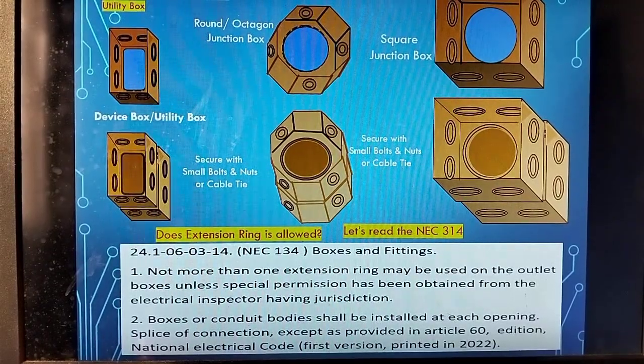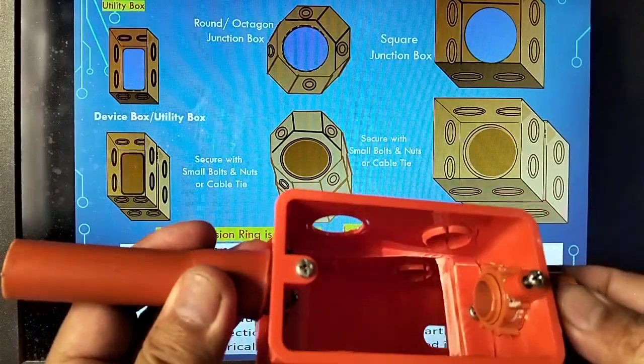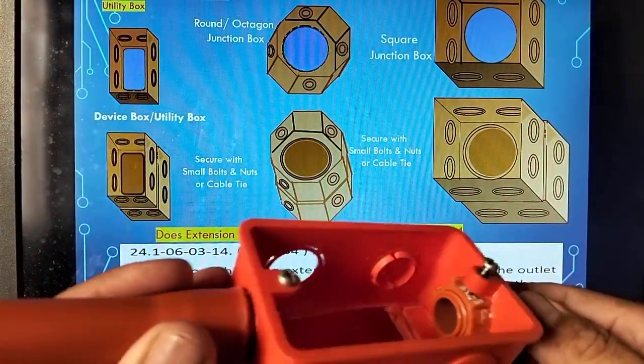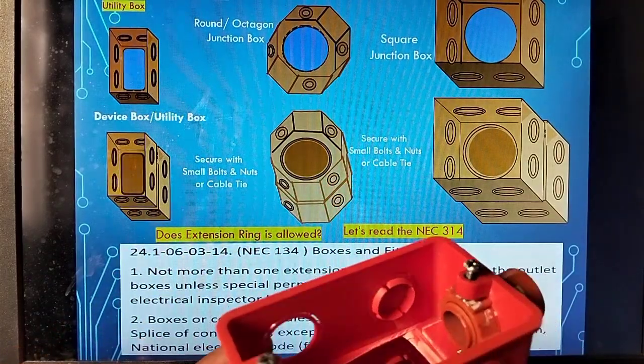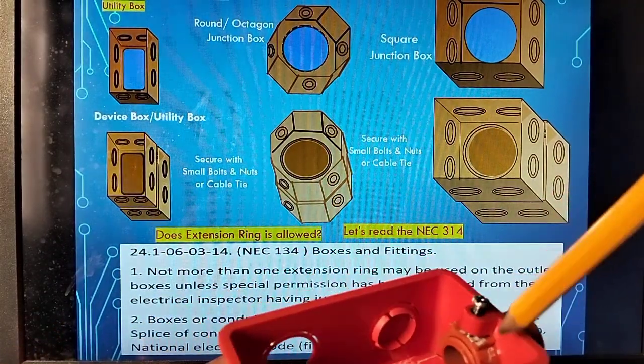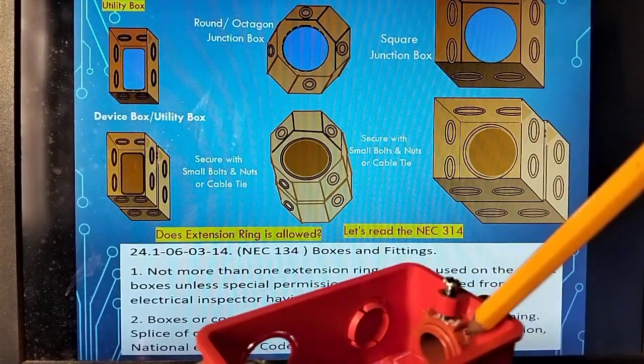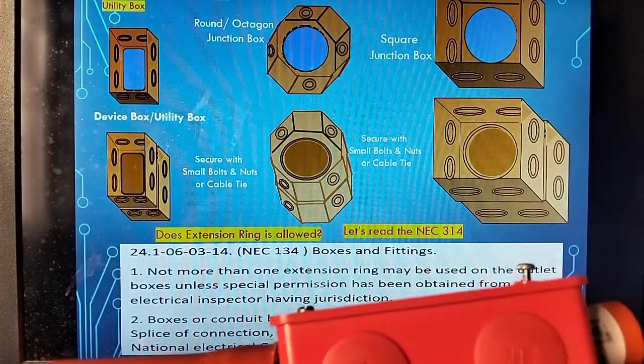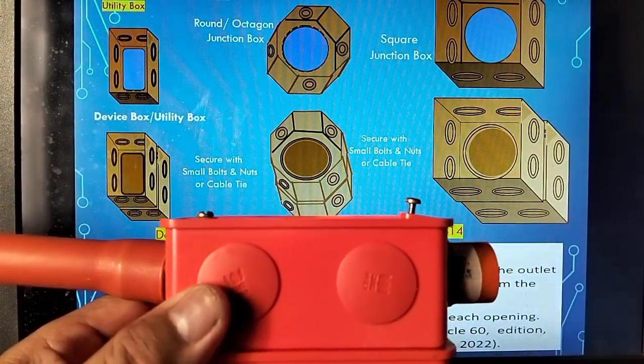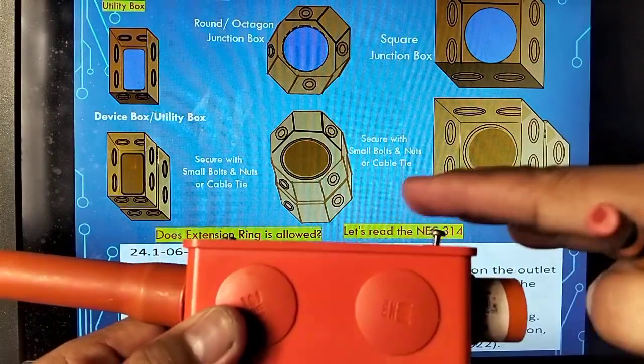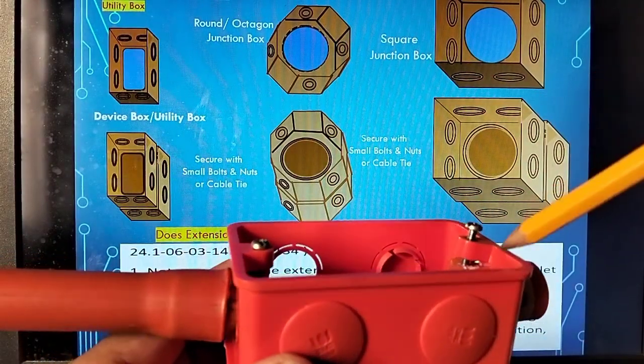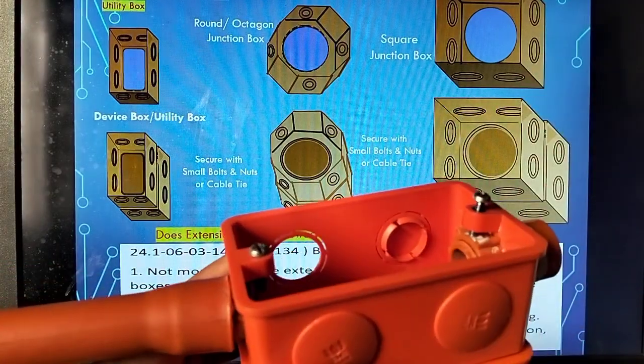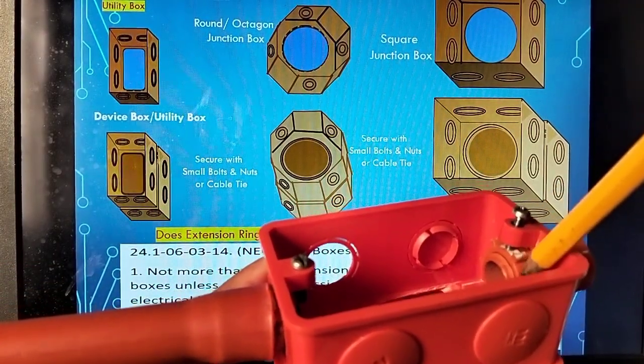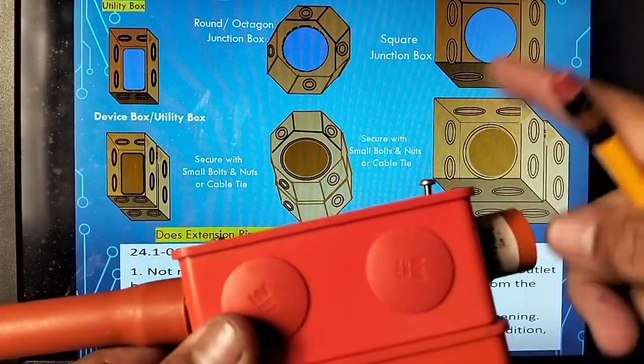Here also, I have something to tell you. If you notice here, this is a device box or a utility box. If you are going to use a conduit connector or pipe connector to secure it using the lock nut, but tendency, if you notice here, see the angle of this screw point is already going outward, whereas it is not yet fully tightened. See, it's already hitting the lock nut. So tendency, this will be broken and become useless.